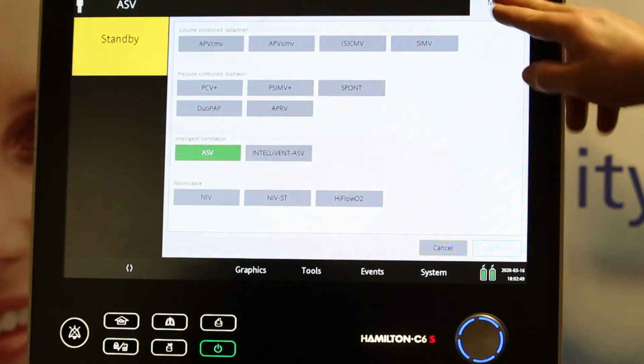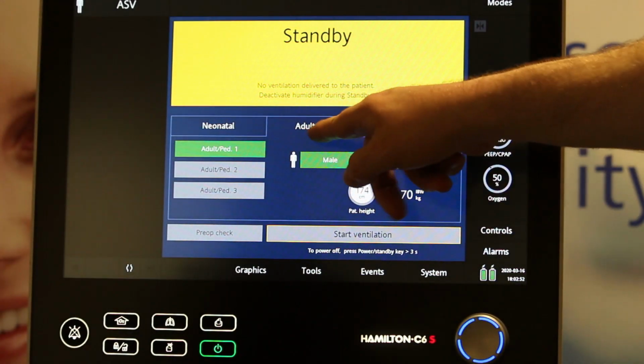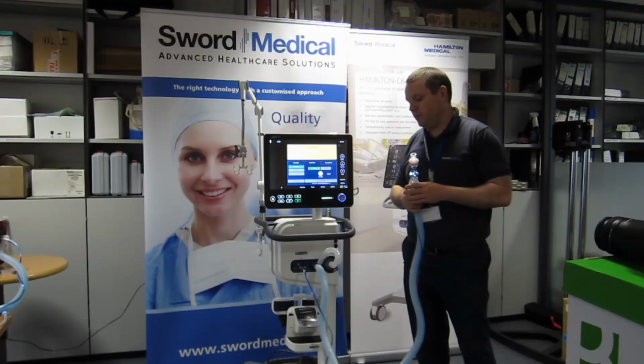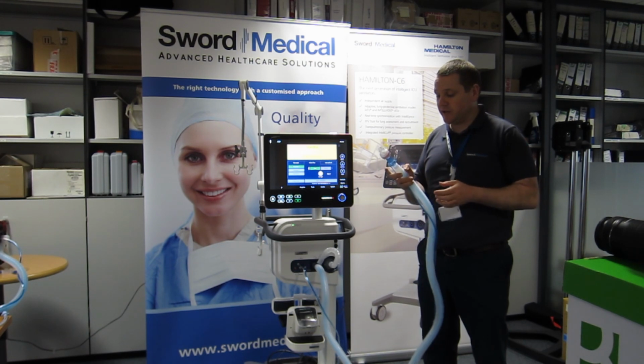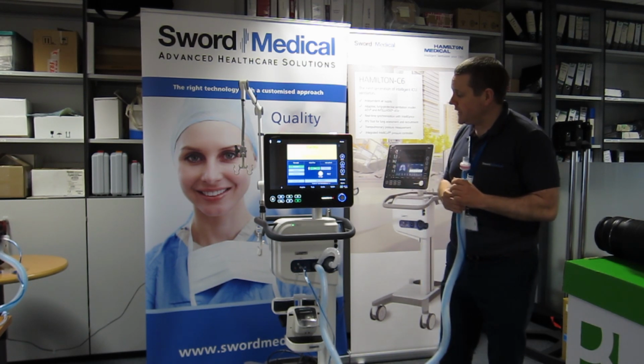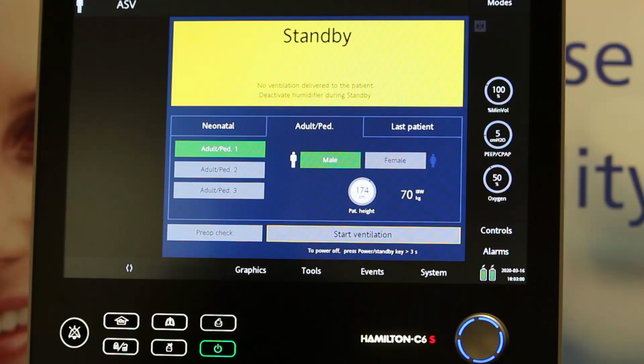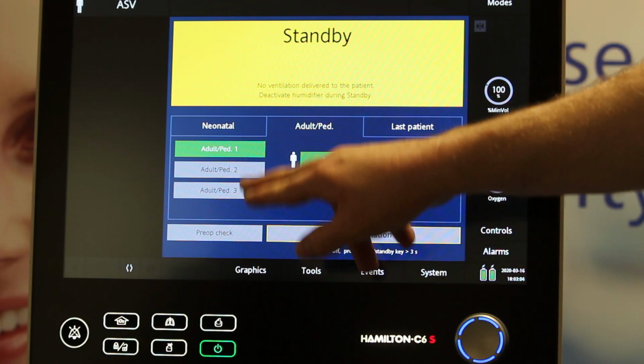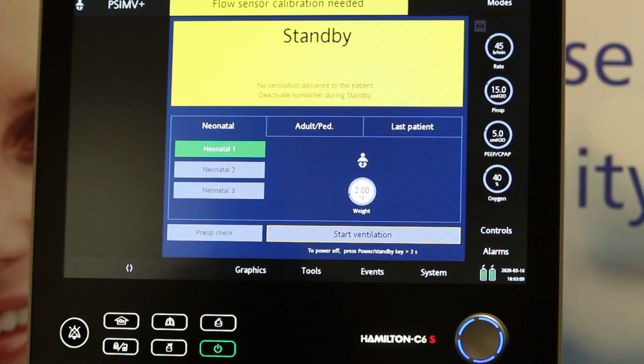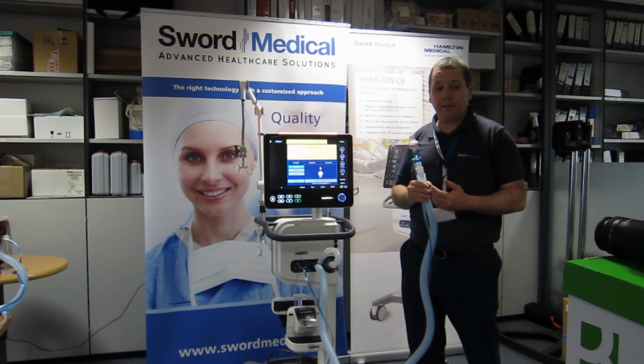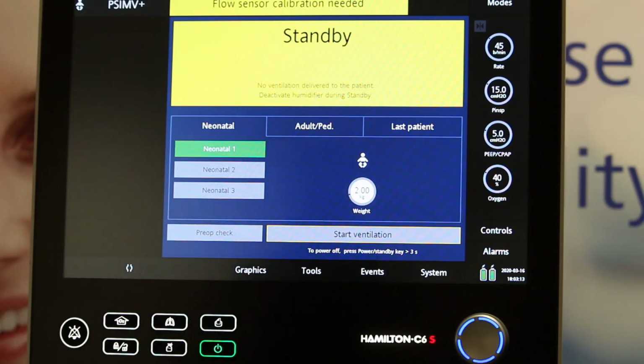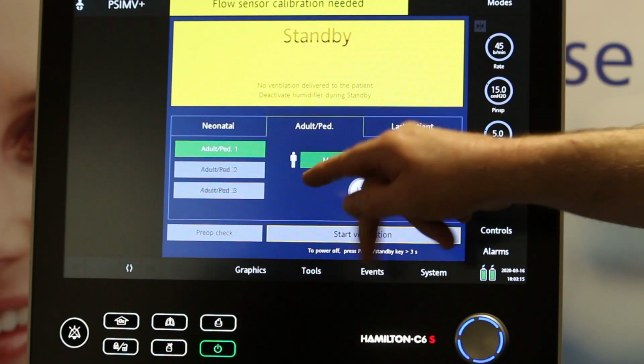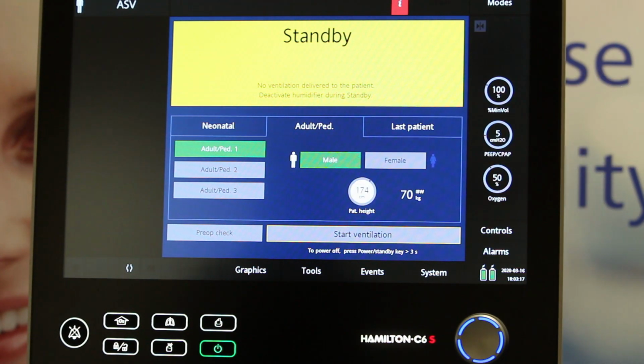So ASV, I'm going to start running ASV, and just go back to the home screen here. You can see we have our adult pediatric ventilation modes. This is an adult pediatric circuit, so that will do patients from 3 kilos up to full adult, 3 kilos being average birth weight. Then we also have 3 shortcuts here. So if you have 3 modes that you use a lot, you can put them on the front screen. There is also a neonatal mode, and that'll do patients from 200 grams up to 30 kilos. The neonatal takes a different flow sensor. So we're going to mainly be using adult pediatric.